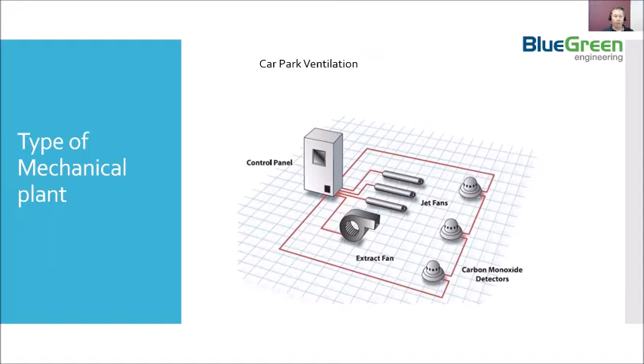And there's a standard, 1668.2, that says if there is no carbon monoxide detector, the fan should be operating 24/7 at 100%. So people do use timers on this, but it's probably not as per the standard, and it also poses risks, because having a timer, there could be times of the day where the carbon monoxide levels rise above limits, and that can be dangerous because carbon monoxide is odorless and could be deadly as well.